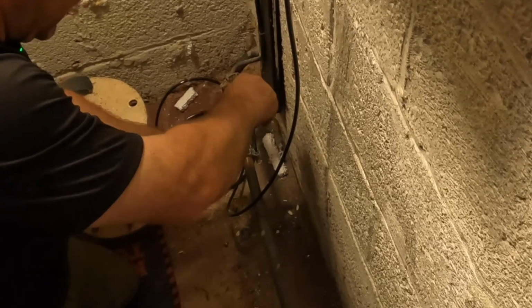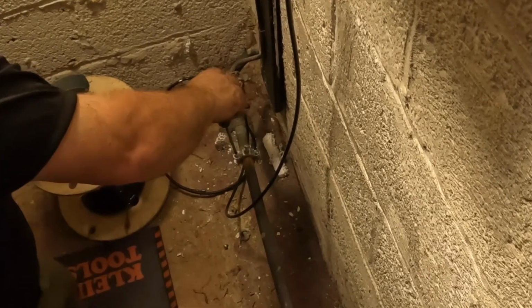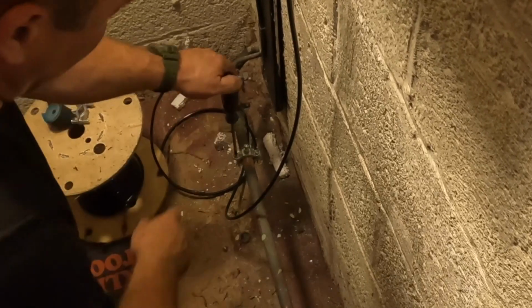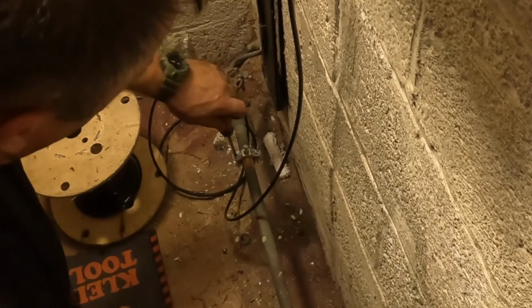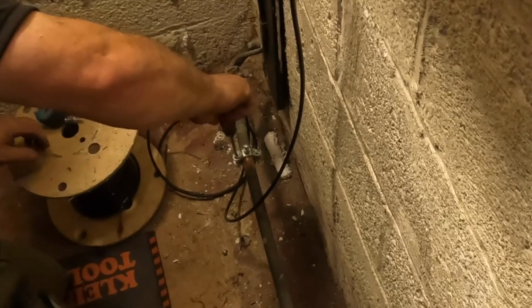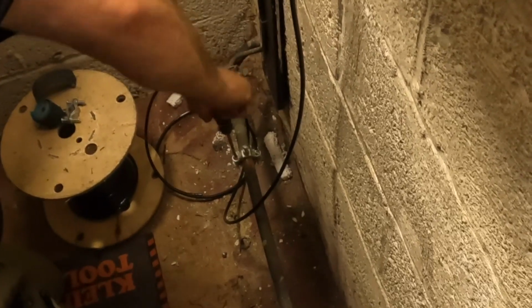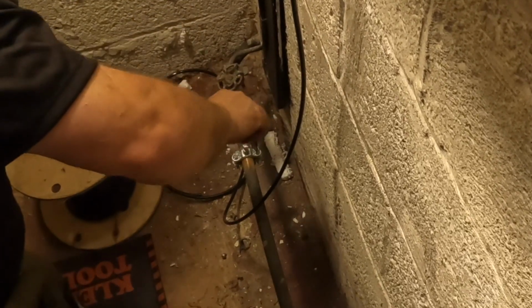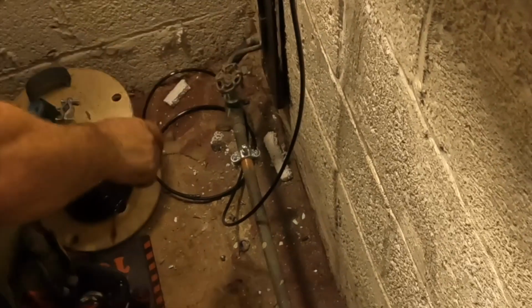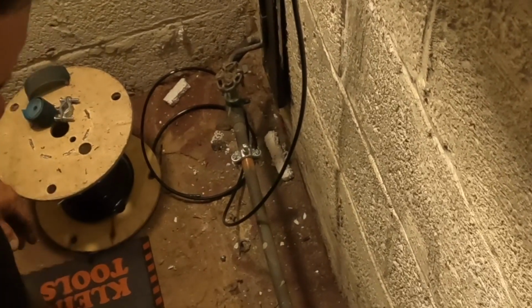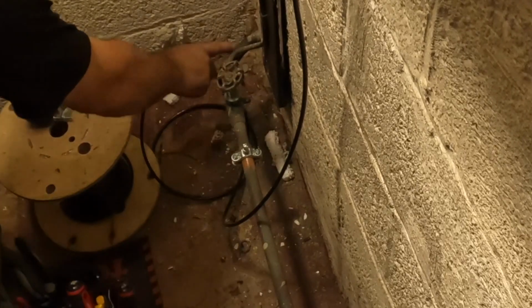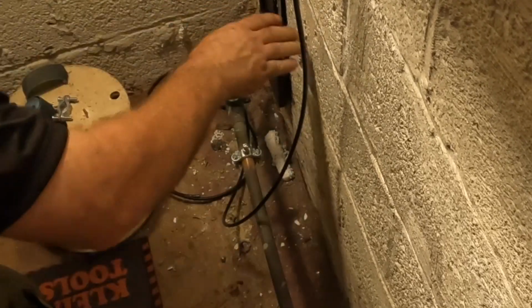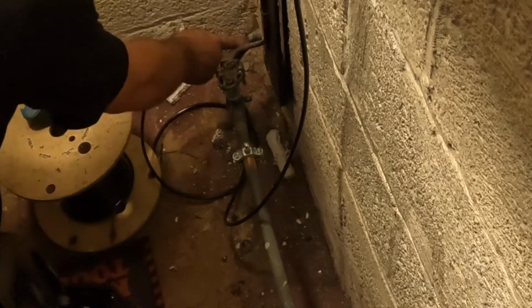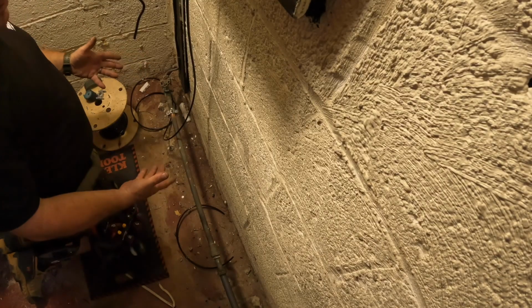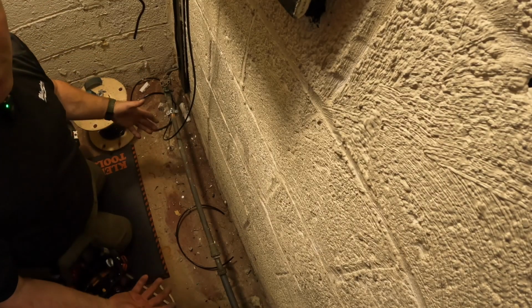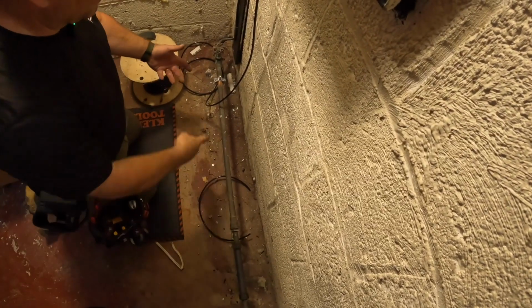So you'll notice, like the last house in South Plainfield, we did the service upgrade there. And I'm only thinking about that because I was there yesterday to meet the inspector. It passed inspection, no problem. But like the house in South Plainfield, this house here has a water meter outdoors. So you still need to bond it because this section right here goes through the earth out to the city water. All right, so because this copper is embedded into the earth, and the earth, as Mike Holt always says, the earth doesn't have terminals.